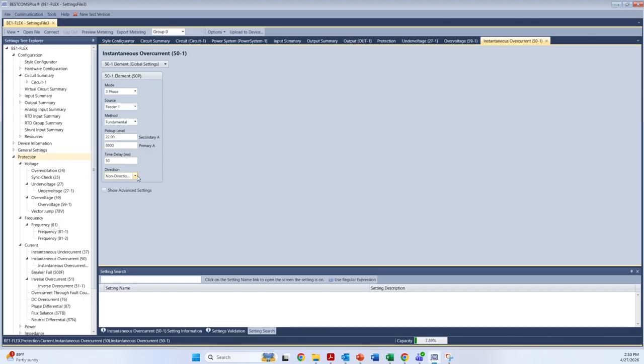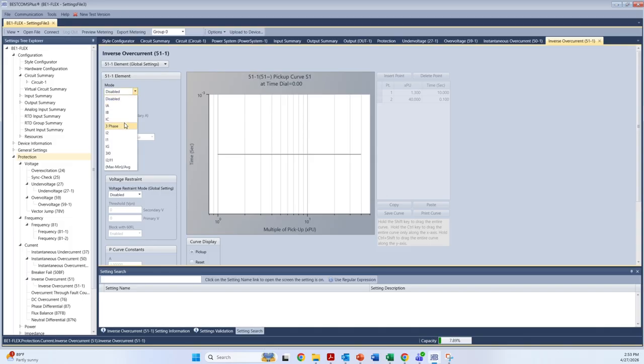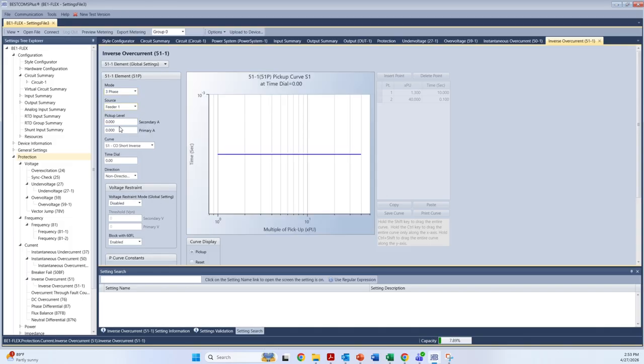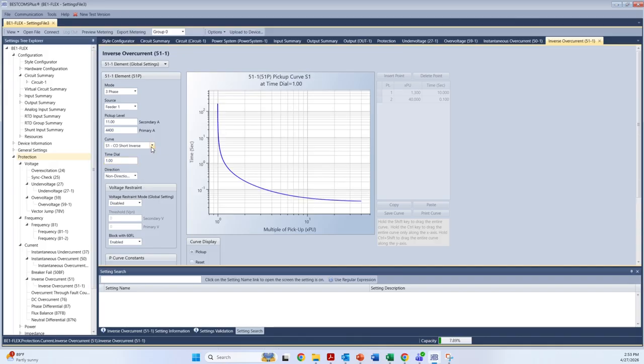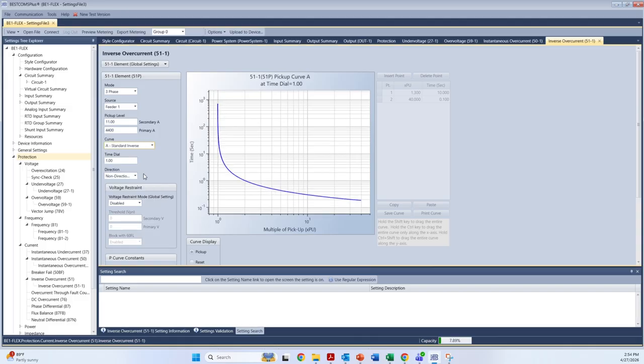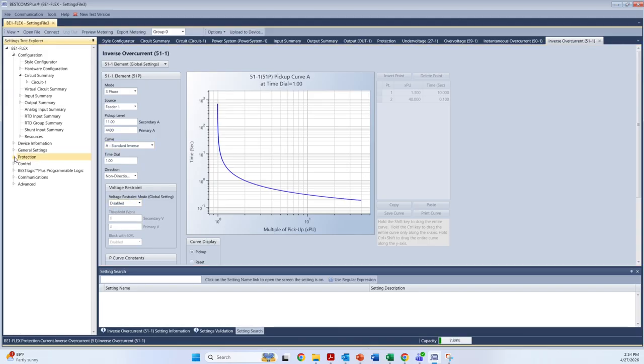Time delay again, and then direction if you want to use directional. 51, time overcurrent. Here again, selecting the source, the pickup level, time dial, and you also have to select the curve type from any of these curves. Down at the bottom is a table curve, so you can do a custom curve. I will assume that this one is standard inverse curve. And then voltage restraint or control if you need to use those functions as well.